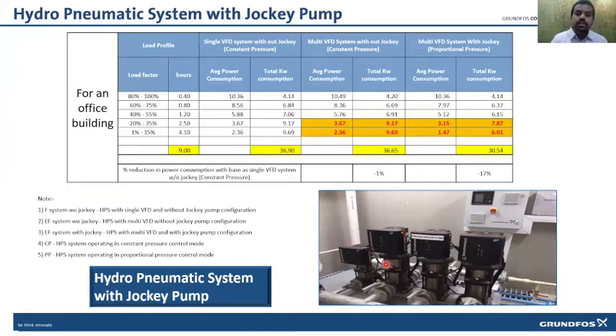So what we did is we introduced something called a jockey pump or pilot pump, which is designed at 20% of the main pump capacity. So whenever we have a lean load or a load closer to 20-30%, this pump will take over and operate with higher efficiency to maintain the same system efficiency at all the loads. So this is again just a comparison. When we have a multi-VFD system with jockey pump with proportional pressure, we end up saving 17-18%. It's again life cycle data. So the jockey pump, of course, brings a lot of savings when we operate at part load or lean load condition.